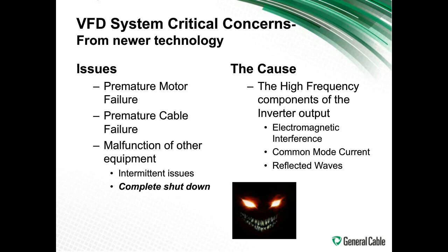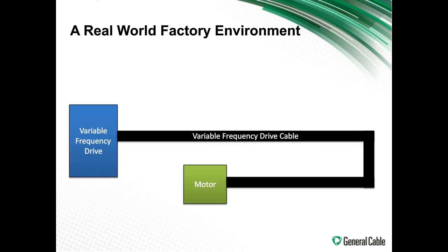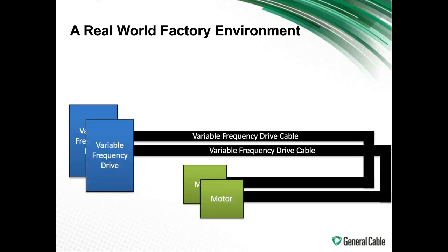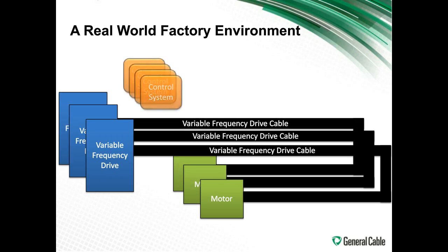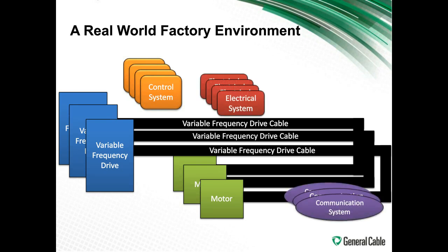We'll go through this. So in a real world system, you would have the frequency drive, a variable frequency drive, connected to the motor with a longer length of cable than we normally would have expected, just because of the way the system is supposed to be. Then you have several of them. You don't just have one. And then along with that, you have different control systems. You have electrical systems, communication systems, and people. So there's a lot of chaos happening in this manufacturing environment.